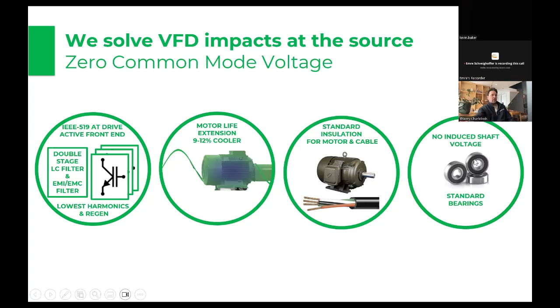And then, of course, common mode voltage, which is a pain to most facilities because their motors break down so quickly from the bearing side of things. You don't need to add these chokes. You don't need to insulate your bearings, and you don't need the shaft grounding rings. By the way, if you've got hazardous location motors, let's say they're Division 2 atmosphere, you may have to insulate both bearings to avoid the shaft grounding because it may be considered a sparking device. You don't have to worry about that anymore. Our drives can sit as far away from the motor as you want, and they do not have to have insulated bearings or shaft grounds. And that's because we don't induce the voltage. You can use standard bearings.